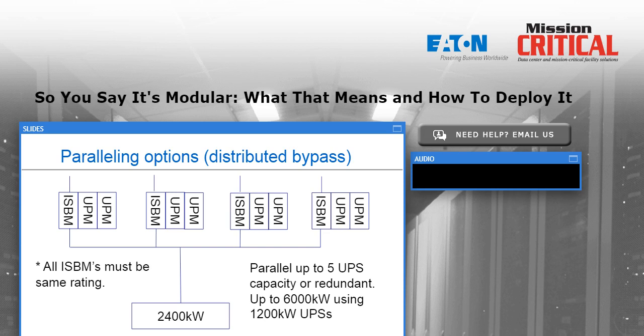That being said, in the smaller UPS environments, let's say 60 or 75 kVA and below, there are some modular UPS systems that have a discrete battery dedicated to each slide-out power module. That way, the battery connections are not common across the multiple power modules, so a problem in a battery module would only affect its associated power module, allowing the remaining power modules to run on battery and get the full capacity of their integral battery. So that's the ultimate in redundancy there. But when you get into the larger systems, that kind of scheme becomes awfully expensive and space intensive. So generally you will see in a multi-module UPS system or a modular scalable UPS system, there will be a common battery for all the little UPMs that make up that system.